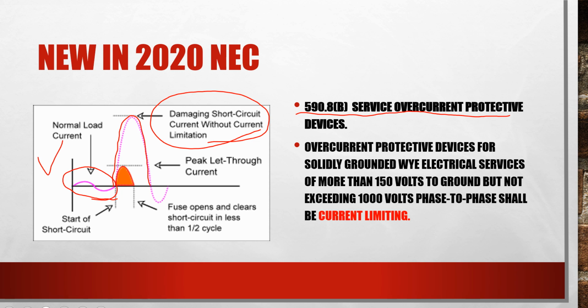So a current limiting device, as you see, really has a peak let-through current, and then it stops. It says, okay, I'm going to shut you off. And as you see, this could happen in less than a cycle or half a cycle. One cycle is 1/60th of a second. One half of a cycle would be 1/120th of a second. So it's very quick to react to this fault condition, which is a good thing.